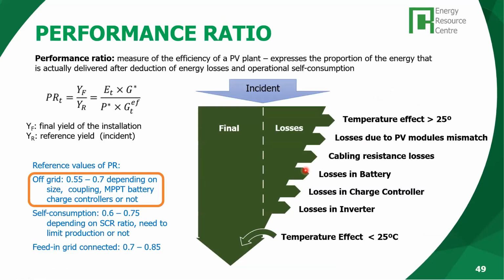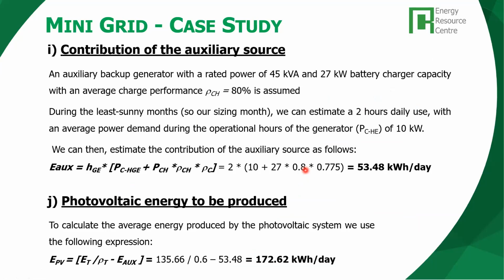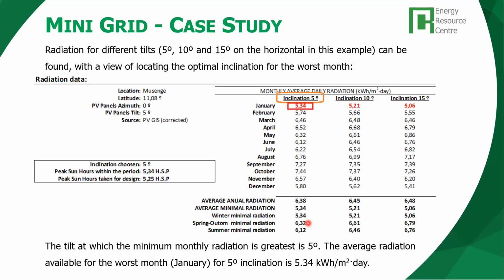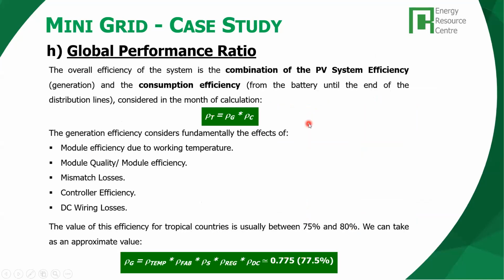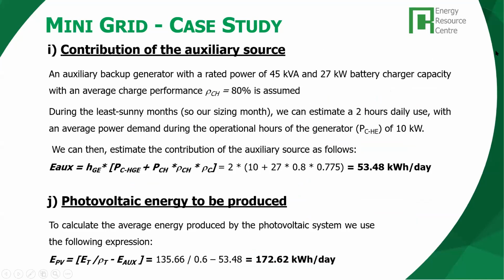This is why for this case, for this location, we consider the use of an auxiliary generation source, diesel generator in this case, okay? Only to cover what would be the gap between the average radiation level 6.3, 6.4, and this reduction found in December, January, February. So this little gap here with 2 hours daily use of the diesel generator is enough, okay? And we can have a diesel generator, small capacity, 10 kilowatts, 15 kilowatts. So we took 10 kilowatts, okay?